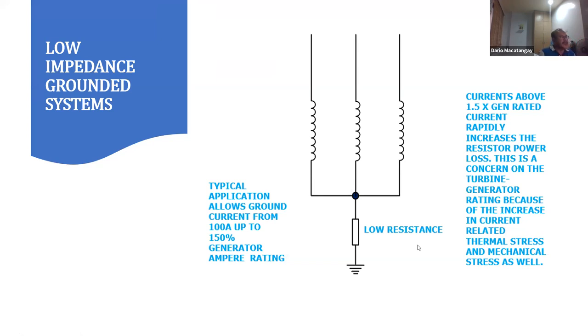In a solidly grounded system, the resistance is really low, so there is not much resistance. The majority of the fault is inductive, reactive in nature. There is no component that needs to be dissipated.